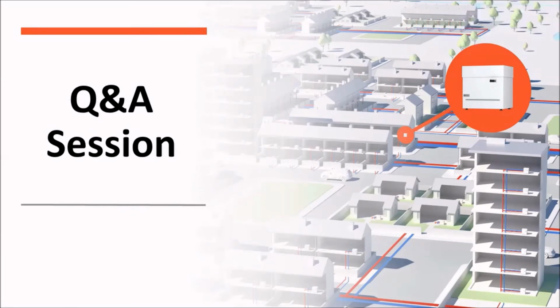Can you provide links to some examples of the radiators that we use? Yes, we just use normal off-the-shelf radiators, nothing special - Stelrad, Dimplex, whatever you want to use, you can put on. The only difference is in the sizing. We size them for the flow temperatures we're going to use, typically 45 to 55 degrees depending on the install. As David said, if we're running at 50 degrees, they'd be about 2.5 times the standard rated output, but other than that, you can use your favorite brand.